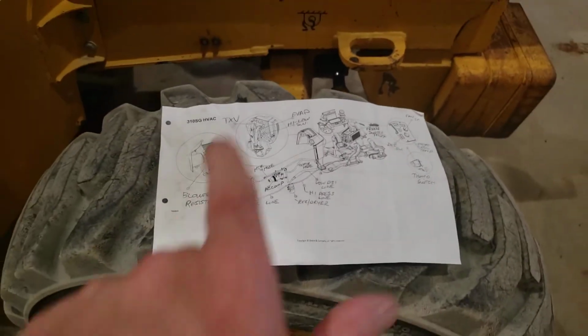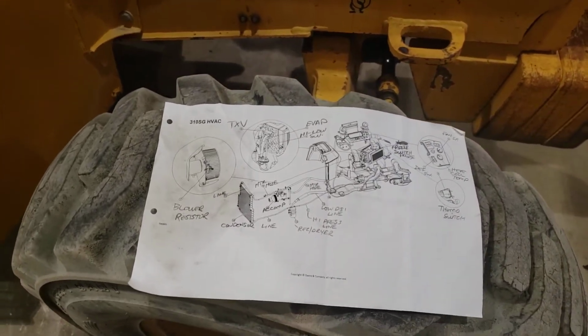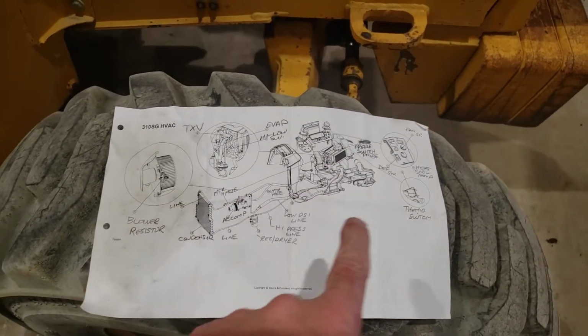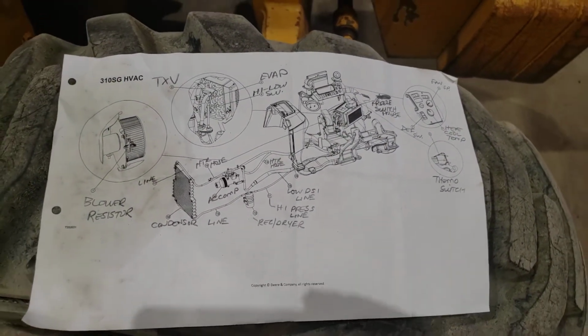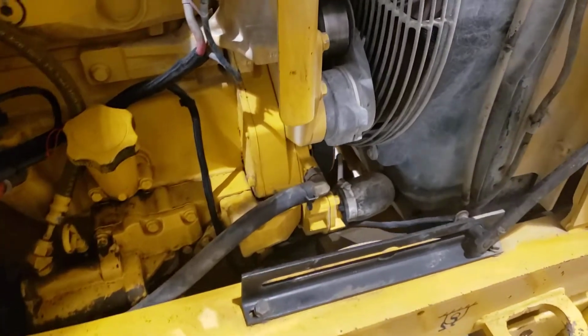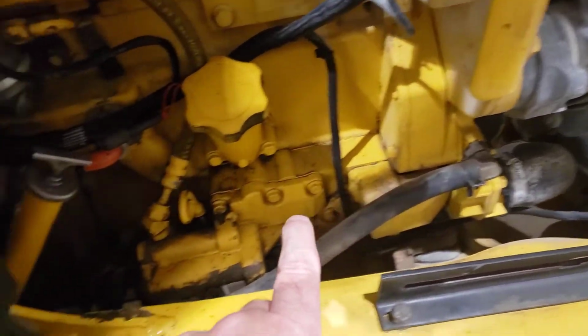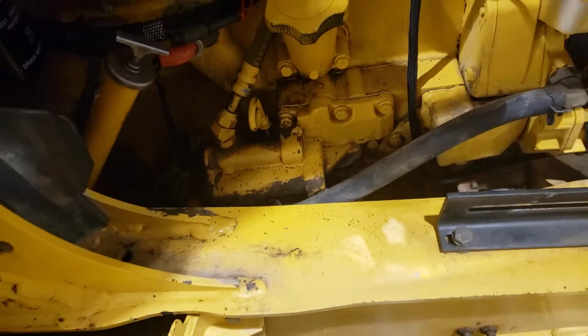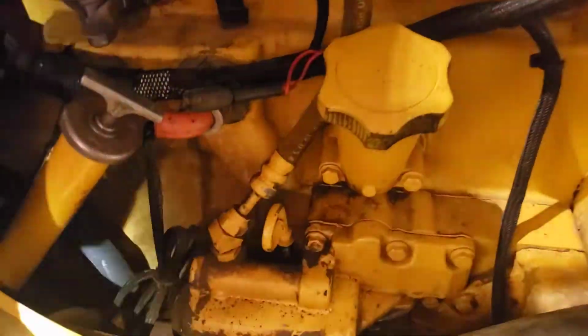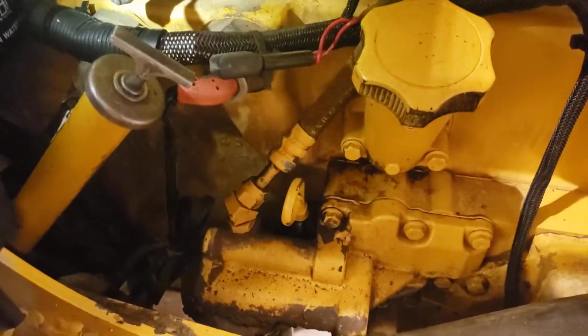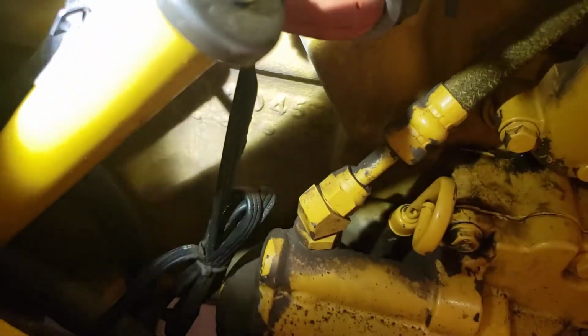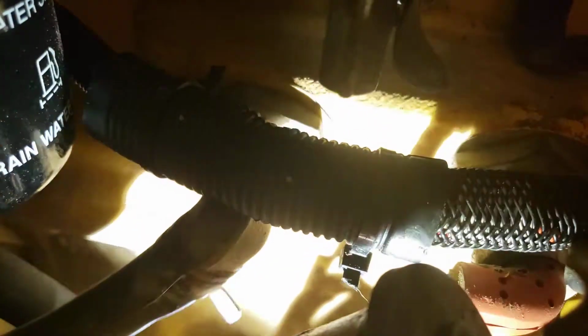So at the completion of this, you should have the drawing labeled, and you should be able to identify any of the parts on this system by their image in the drawing here. So I'm going to start, like I did on the last machine, with the heat supply. So heat again comes from a water-cooled engine, and coming off the side of the block down in here, I see an elbow there and a spring clamp, and that's just next to where the block heater is, actually in the side of the block.